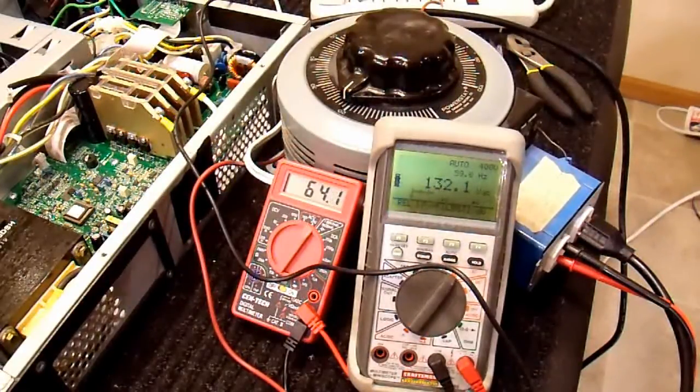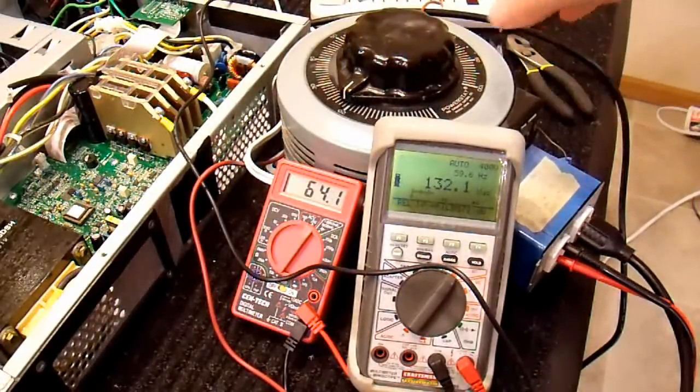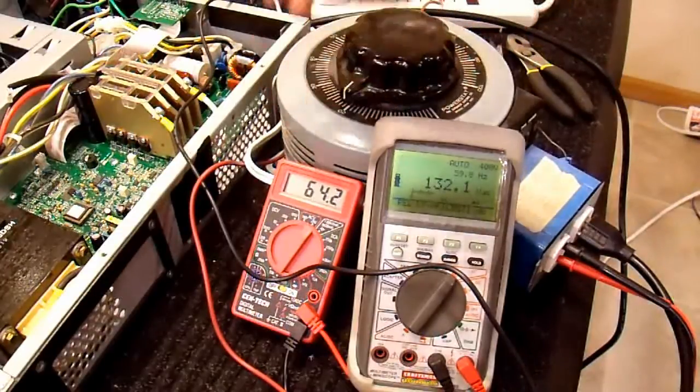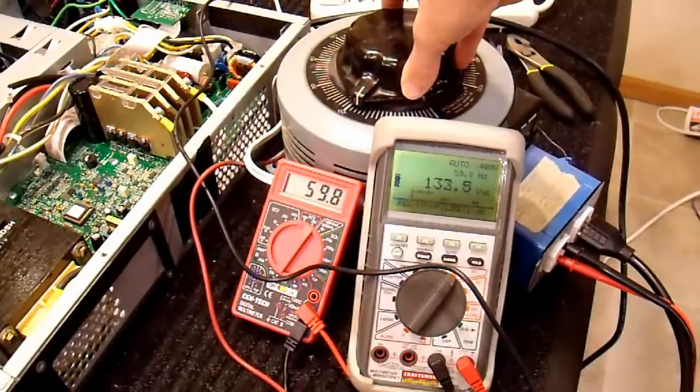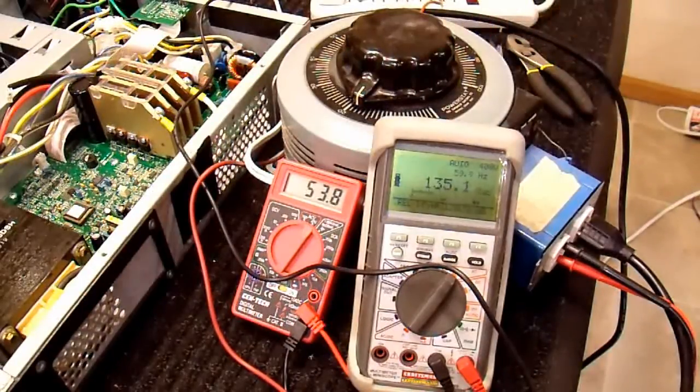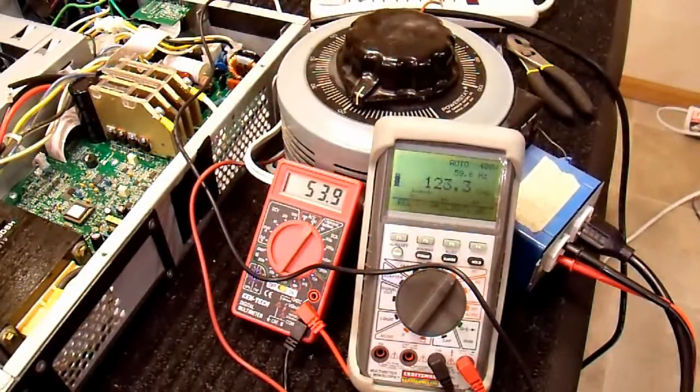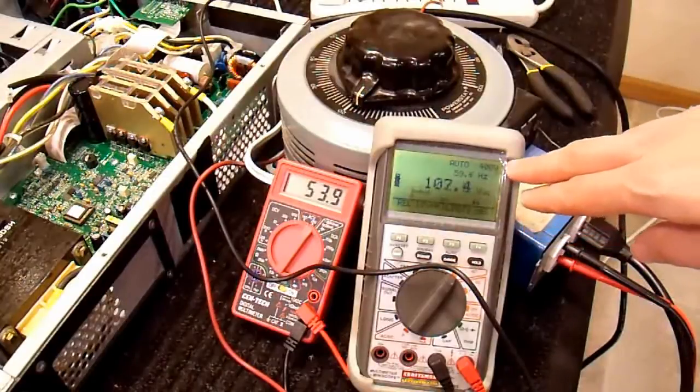You can see that it's just under 60 hertz. And the output of the UPS is perfectly in phase with the wall power. Now I'm at about 64 volts input to the UPS. If I turn this down a little bit more, down to 50 volts or so.